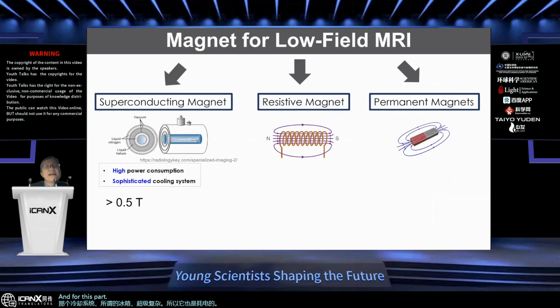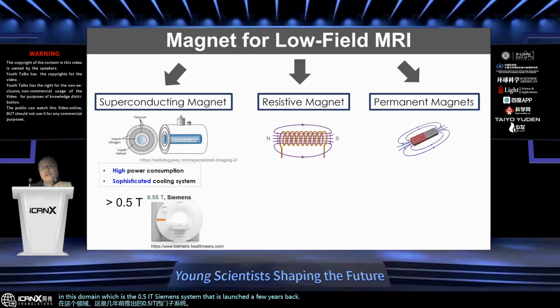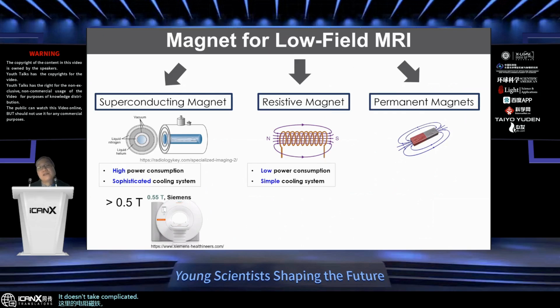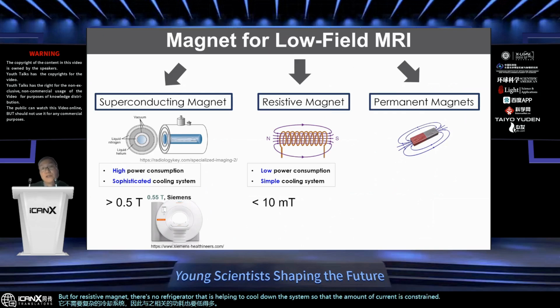For this kind of MRI scanner at low field, the strength is normally greater than 0.5 Tesla. There's one product in this domain, the 0.55T Siemens system that was launched a few years back. For the resistive magnet, as it doesn't need a complicated cooling system, the power consumption associated with it is also much lower. But for a resistive magnet, there's no refrigerator helping to cool down the system, so the amount of current is constrained, and therefore the field strength is also constrained. Normally, the magnetic field it can offer is less than 10 millitesla.